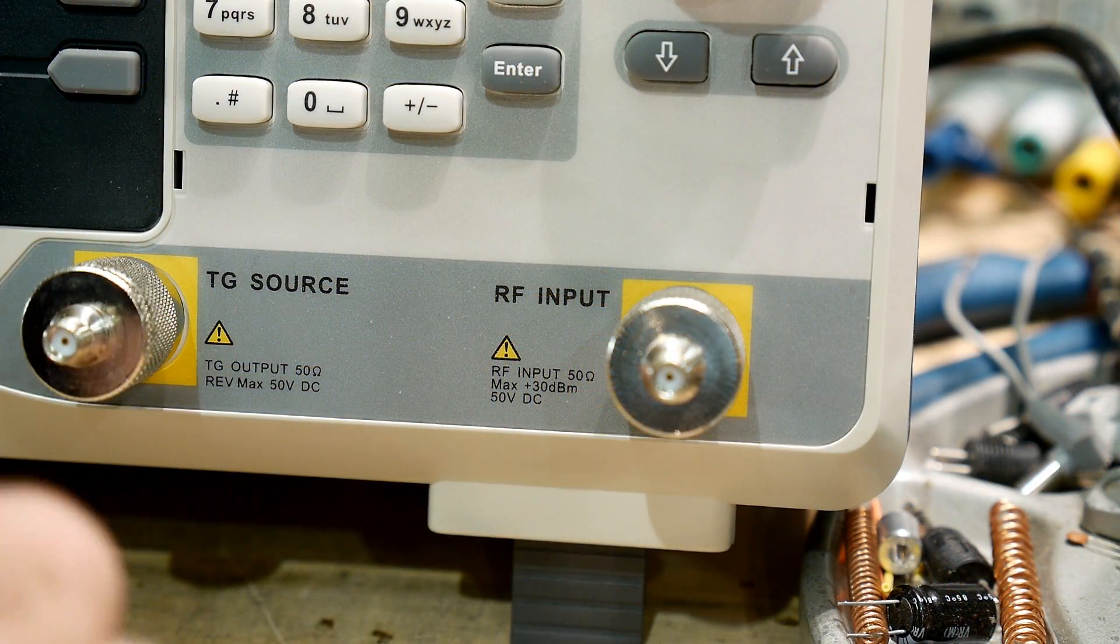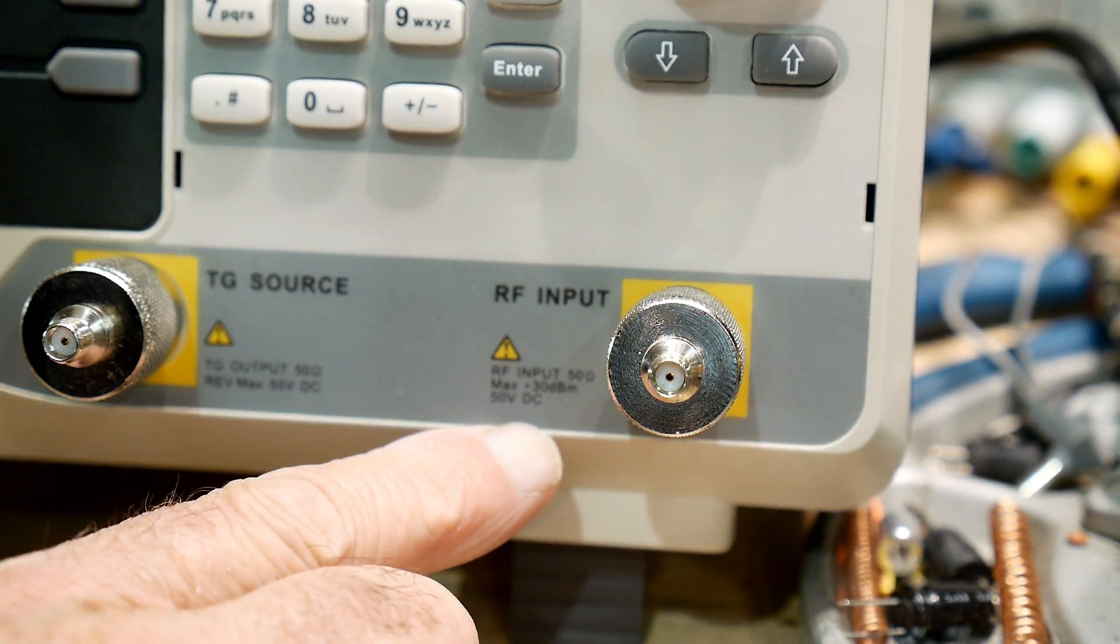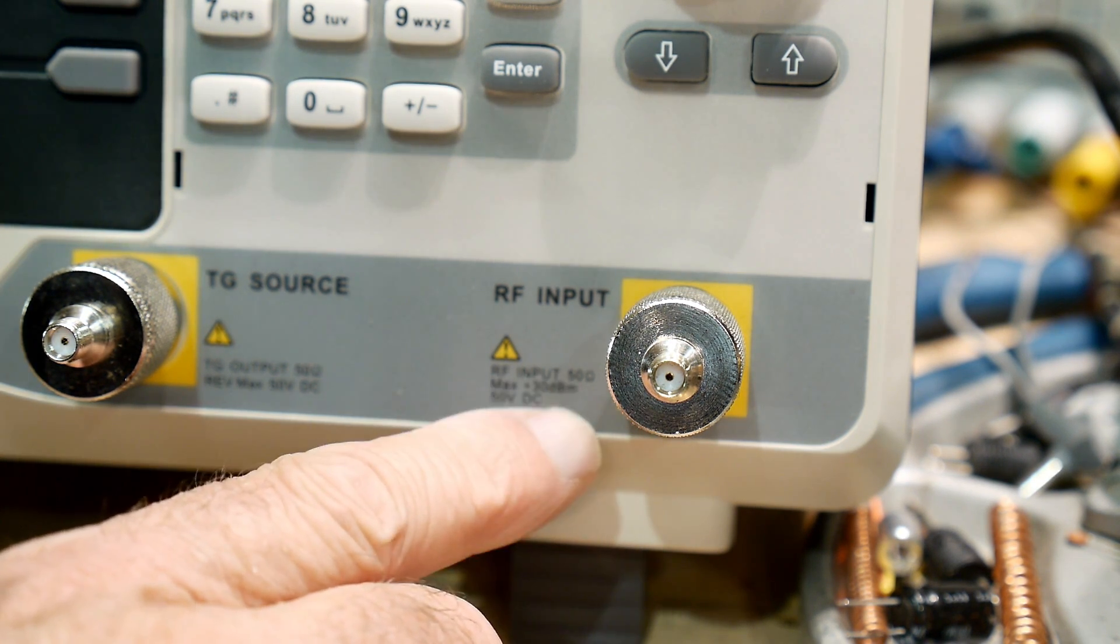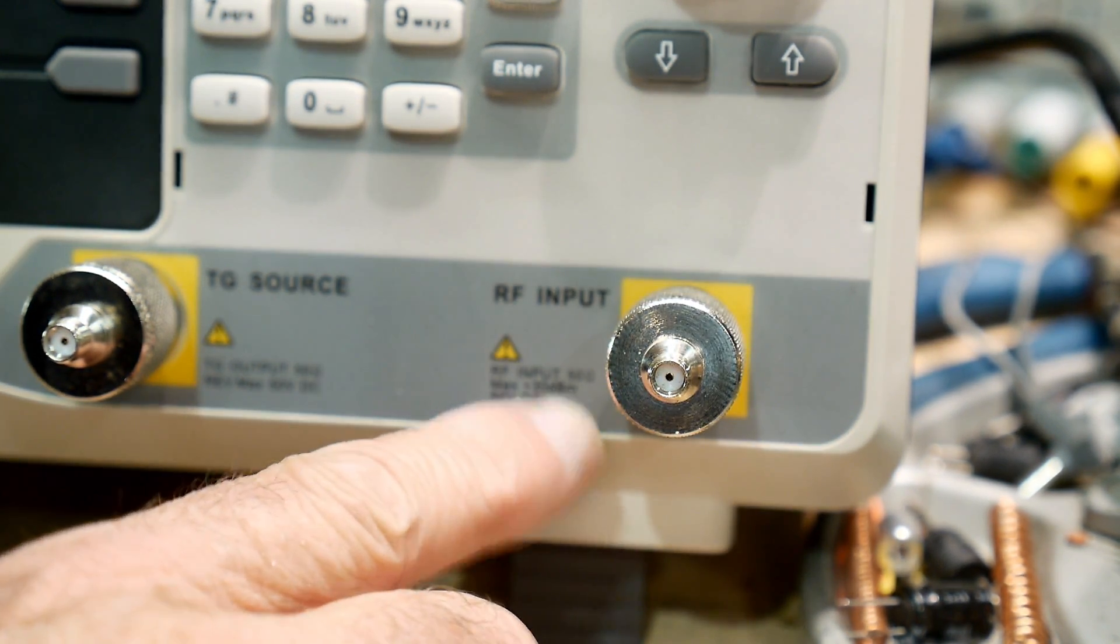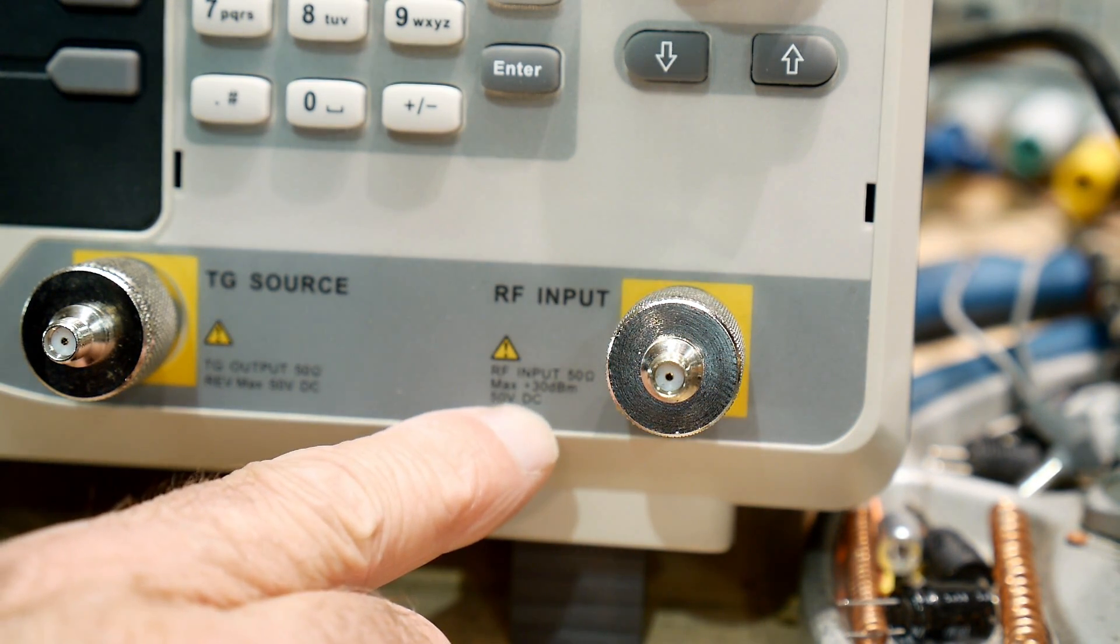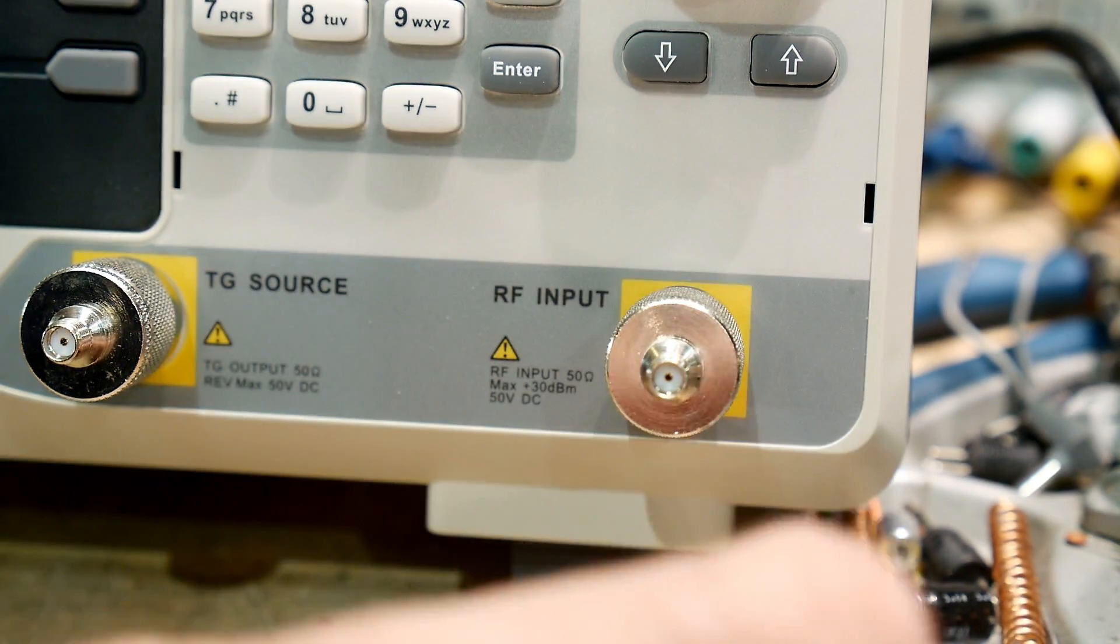One of the nice things about this instrument, it's the exact same protection on the input that the Hewlett Packard had. So this has a maximum of plus 30 dBm. So that's one watt. Plus 30 dBm and it has a DC block inside that's good to 50 volts DC.